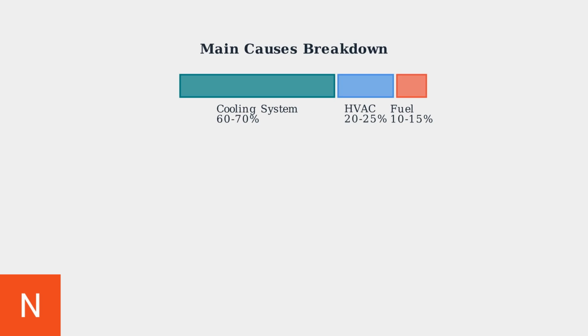The causes break down into three main categories: cooling system issues account for 60 to 70% of cases, HVAC problems cause 20 to 25%, and fuel system issues make up the remaining 10 to 15%.